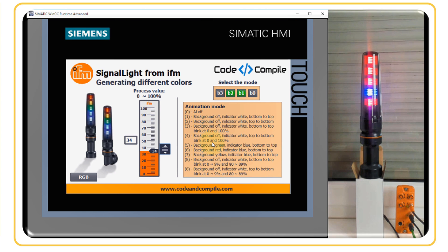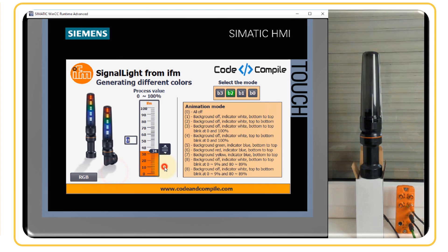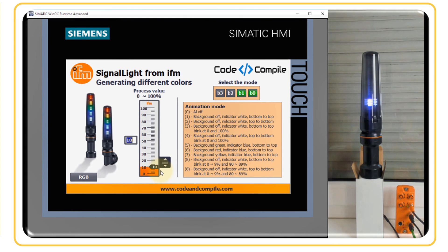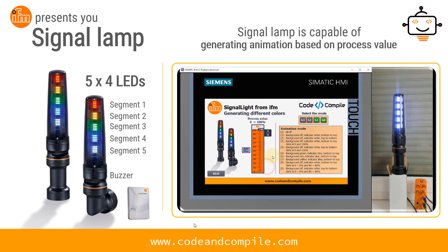Some modes also blink at extreme limits. Mode four: background off, indicator white, top to bottom, blink at 0 and 100 percent. At 0 percent, the top segment blinks. Mode three animates bottom to top and the bottom segment blinks at 0 percent, indicating critically low level. The blinking stops once the value exceeds 0 percent. At 99 percent, all segments are on; at 100 percent, the top segment blinks to indicate critically high level.